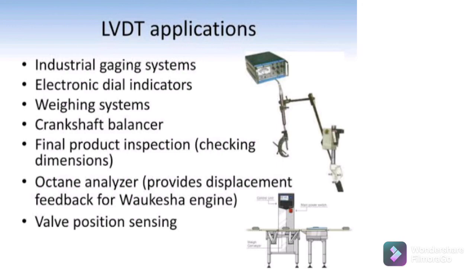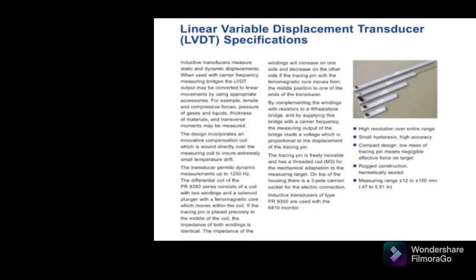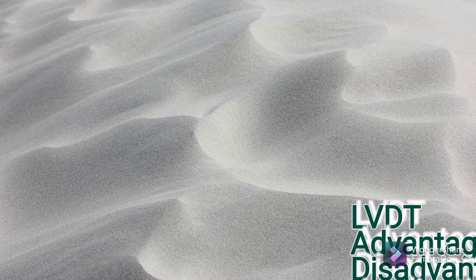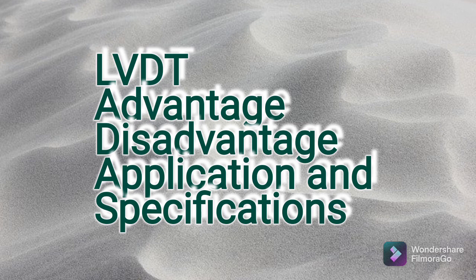Finally, we will talk about LVDT specifications. The range of measurement is plus or minus 0.25 millimeter to plus or minus 750 millimeter. The operating temperature range is minus 260 to 600 degrees Celsius. The last specification is frequency range — up to 500 Hz to 20 kHz. In this video we have learned about LVDT advantages, disadvantages, specifications, and applications.